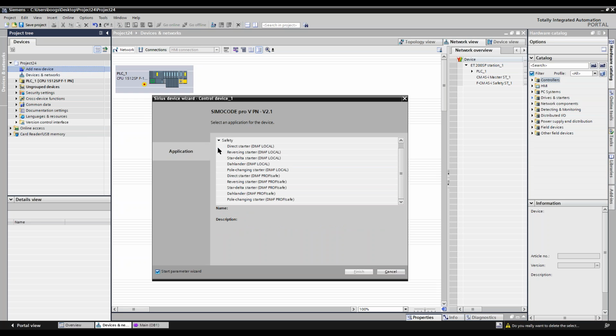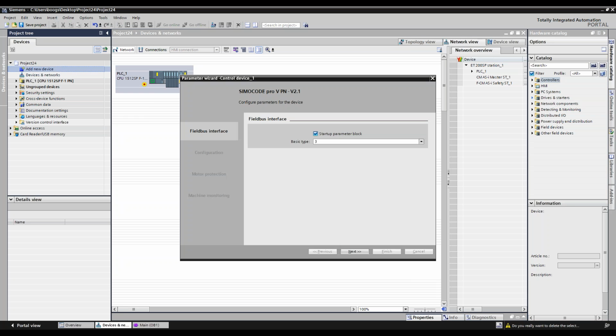But notice that in here, here's the safety side, where I have digital module safety local, meaning it doesn't matter what communication protocol I'm using, RTU, Ethernet IP, Profinet, Profibus, or I do have ProfiSafe, which is in conjunction with Profinet. But I can do safety here. But for today's purpose, I'm going to do reverse starter. And what's going to happen when it hits finish is the software is going to start installing a template for a reverse starter in the SIMOCODE parameters so that it has a standardized way to wire up the SIMOCODE and a standardized way how it acts and reacts to local, remote, forward, reverse, stop, etc.